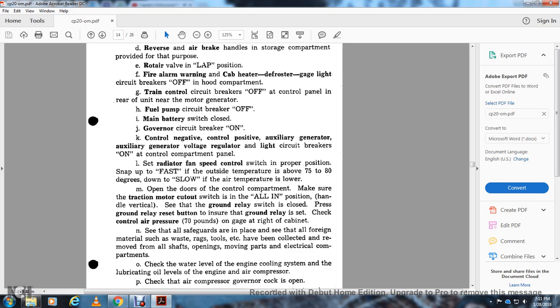Open the door of the control compartment and make sure the traction motor cutout switch is in the ALL IN position, handle vertical. See that the ground relay switch is closed. Press the ground relay reset button to ensure the ground relay is reset. Check the control air pressure for 70 pounds with the gauge to the right of the cabinet. See all the safeguards in place.